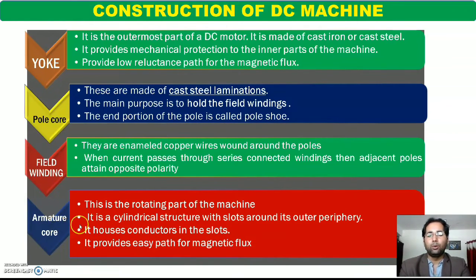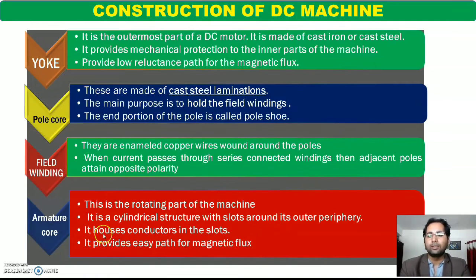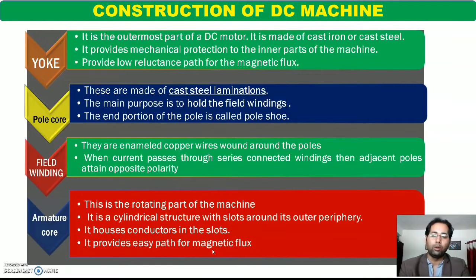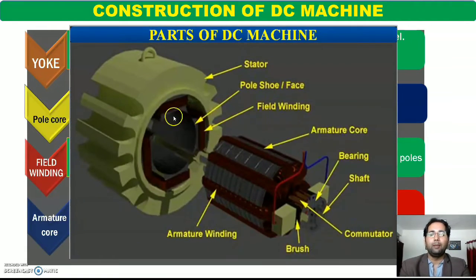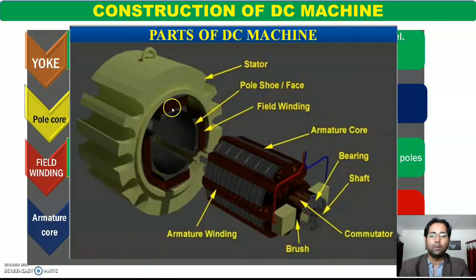Next point is armature core. Armature core is the most important part of the rotor, क्योंकि core वही part है जो rotating होता है — this is the rotating part of the machine. इसका shape cylindrical structure का होता है, और उसमें slots कटे होते हैं — slots इसलिए कटे होते हैं ताकि हम easily winding को उसके अंदर wound कर सकें, यानि it houses conductors in the slots. Armature core के अंदर winding को हम pack करते हैं. This provides an easy path for the magnetic flux — core का application यही होता है, कि यह magnetic flux को low reluctance path provide करता है. यह frame यानि yoke कहलाता है, यह magnetic pole है, यह field winding है, यह pole shoe है — जिसका curved shape है ताकि uniform magnetic flux provide कर सके.